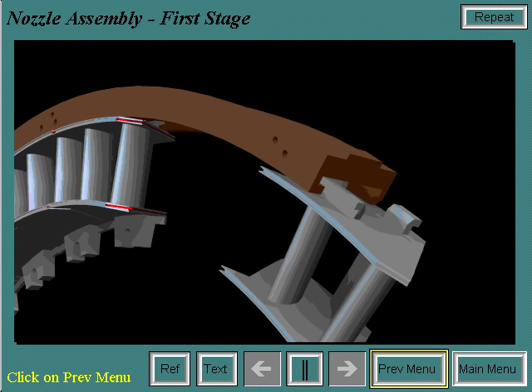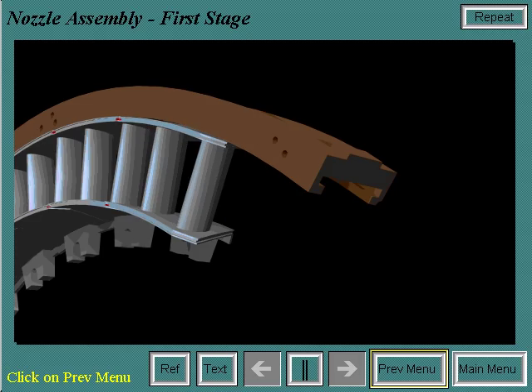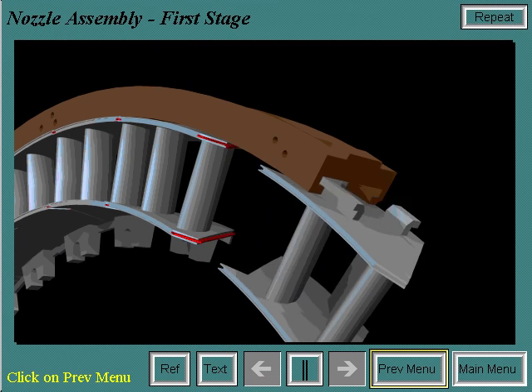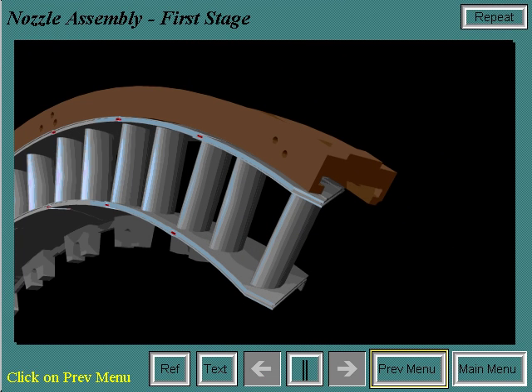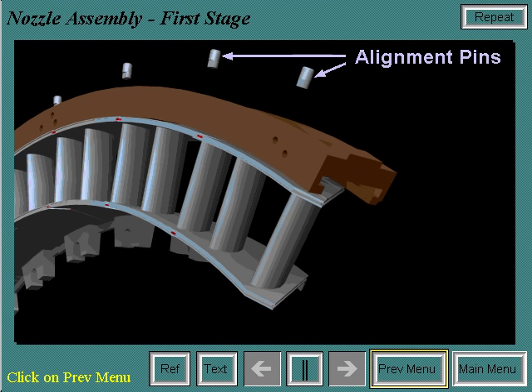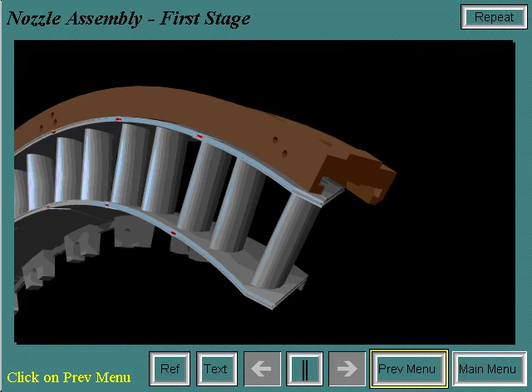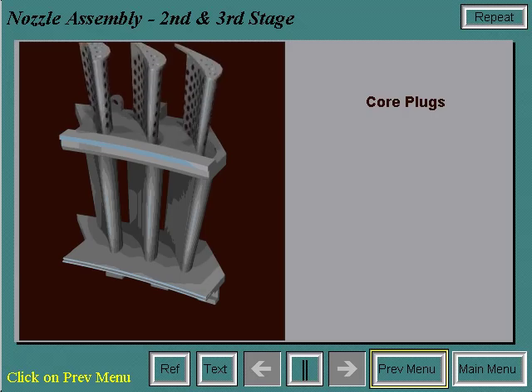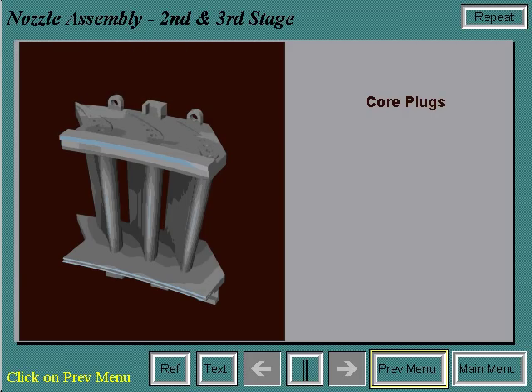To assemble the first stage nozzle, the nozzle segments are installed into the support ring. Alignment pins are then installed to radially align the segments in the ring. To assemble the second stage nozzle, first a core plug is installed in the investment cast piece to allow for even cooling down the center of the bore of the nozzle segment.